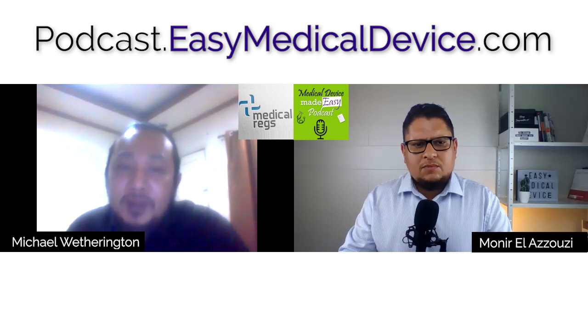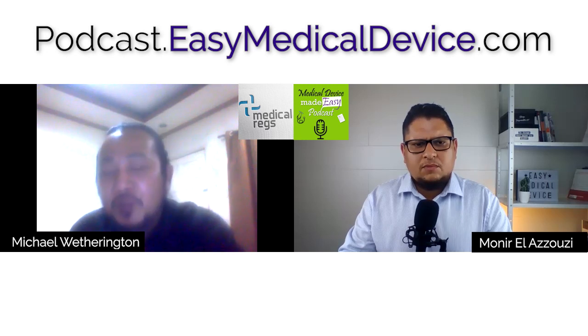That's why, when people start doing the risk analysis, they easily point to the standard name and title as the risk mitigation. But I think it's worth it to be more specific when you're doing a hazard-based analysis. For electric shock, point to a specific requirement in the standard, how you mitigate the electric shock hazard under normal or abnormal condition. Well, how do you determine electric shock hazard? Well, it's based on leakage currents, right? That's why we have patient leakage currents, and then other types of leakage currents that are intended for the operator and the patient.